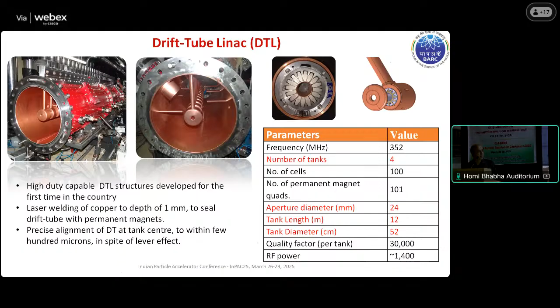The RF couplers were also developed. Again, here the challenge comes from tight tolerances on the iris, which is only 1.5 mm, and the 250 kilowatt power has to pass through that. Again, it is a braze structure. Initially, we tried with the aluminum, benchmarked them, and finally we moved on to the copper-based couplers, which are water-cooled. They are working fine right now.